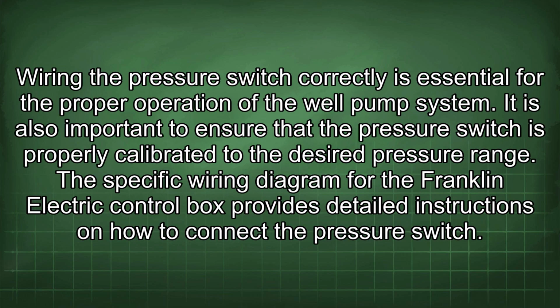Wiring the pressure switch correctly is essential for the proper operation of the well pump system. It is also important to ensure that the pressure switch is properly calibrated to the desired pressure range. The specific wiring diagram for the Franklin Electric control box provides detailed instructions on how to connect the pressure switch.